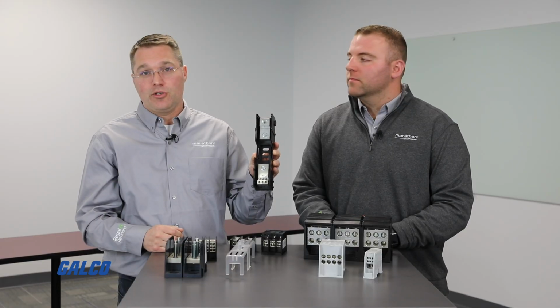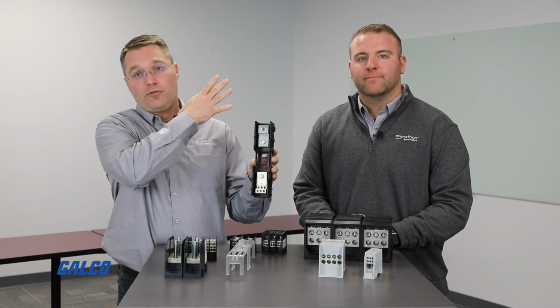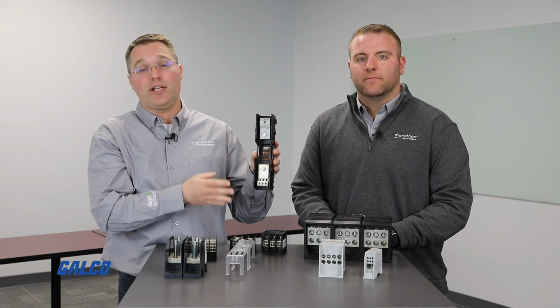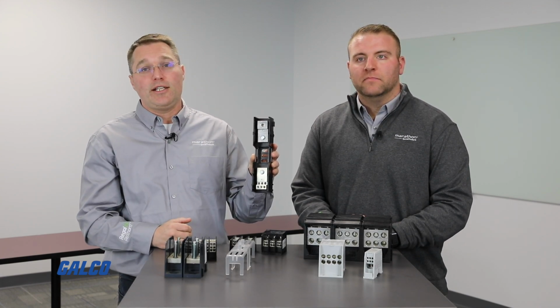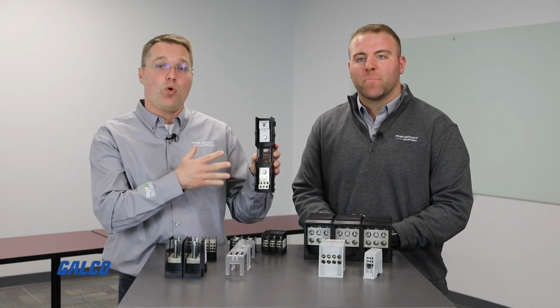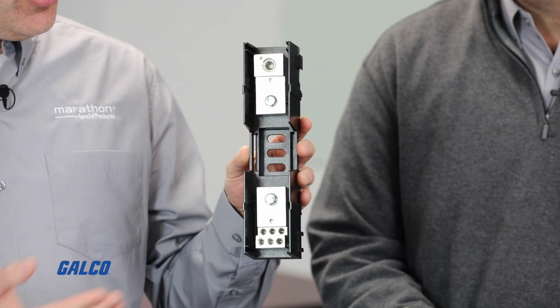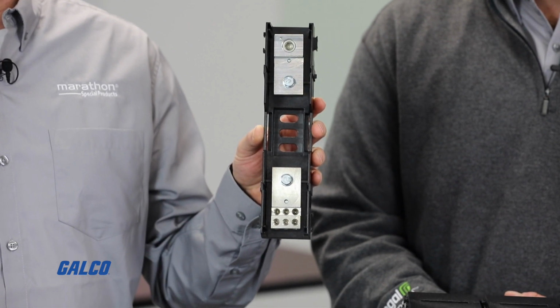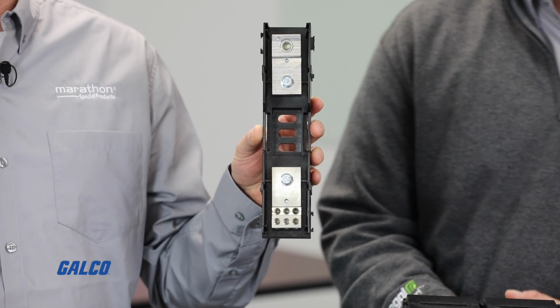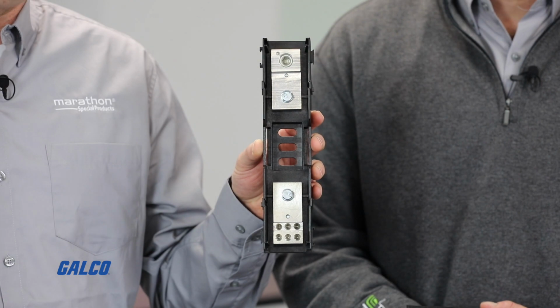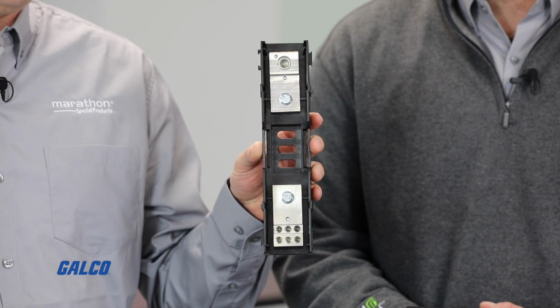A lot of times you're going to have a fuse holder in front of your power distribution block downstream if they need that overcurrent protection. So if you need that, you can save yourself two components in one with this design. The bolt down feature of the fuse makes it much easier to install than the typical pound-in style you'll normally see on the market.